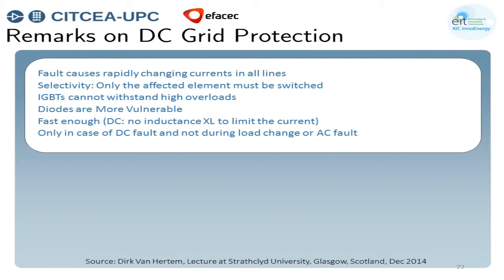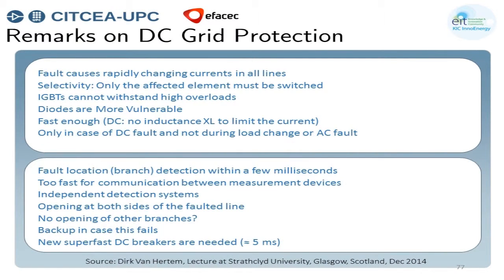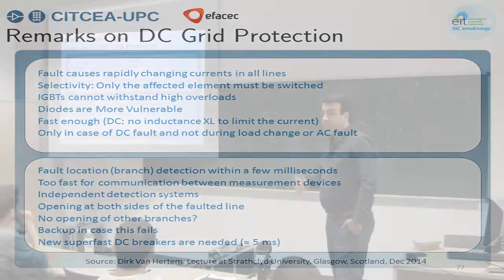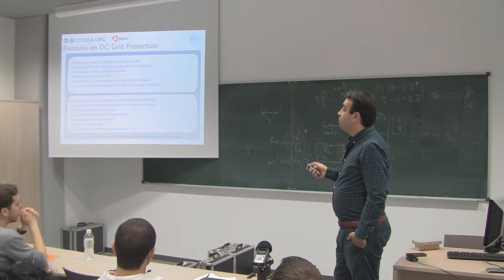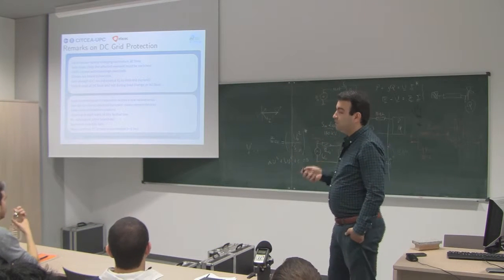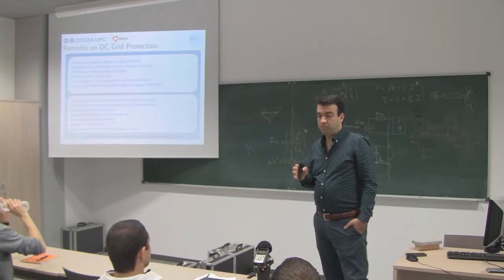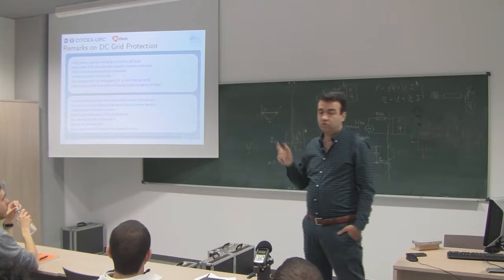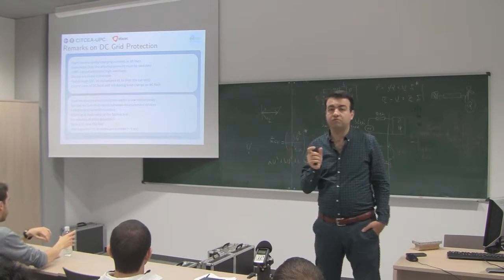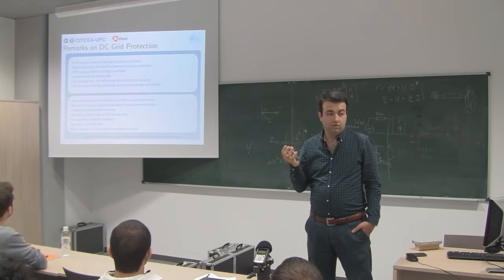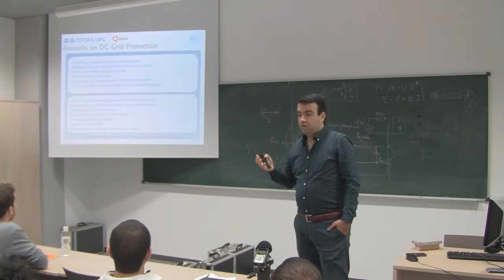So what are the remarks on protection of the DC grid? The protection system should be simple, should be selective, as we have in the AC grid, and should be effective. In the DC grid, selectivity will be a problem because, as I showed you, you have such a small period of time to identify the fault, which is not easy.